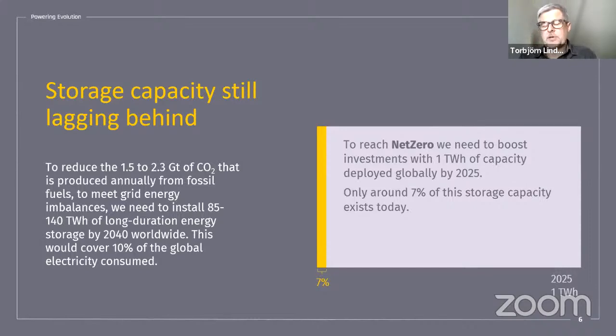Because it's thermal storage, we have 4 tons of melted aluminium in there, and the operational philosophy is to cycle that on a daily basis. It's not designed to charge once during the first week of the month and discharge at the end of the month, because that would be quite expensive. You need to operate your system and produce power continuously to achieve good levelized cost of electricity numbers.